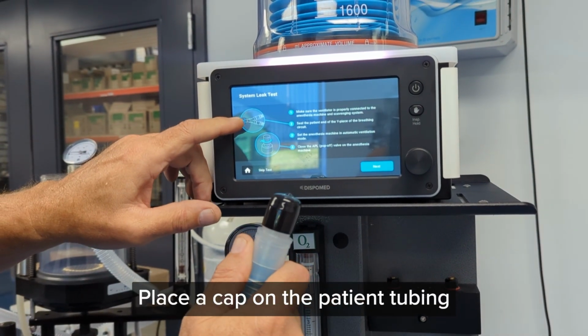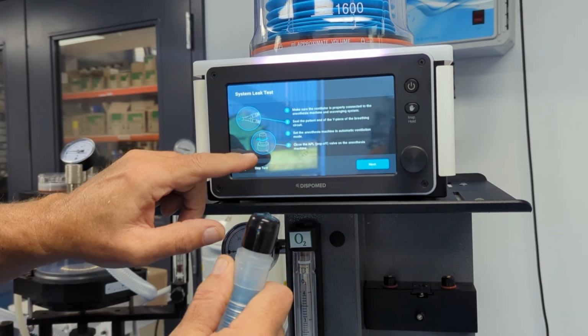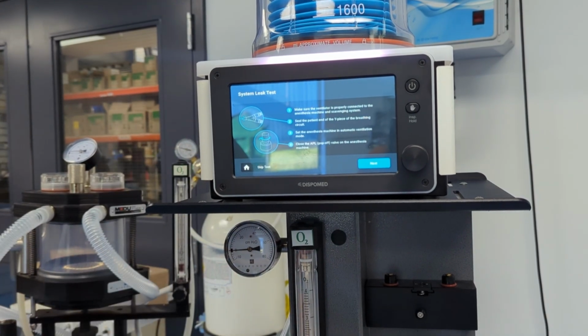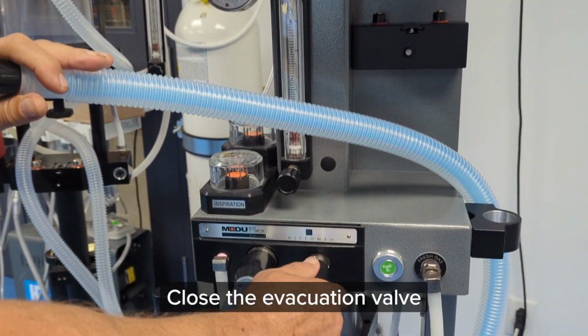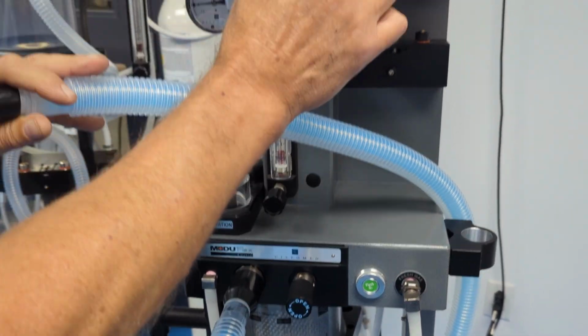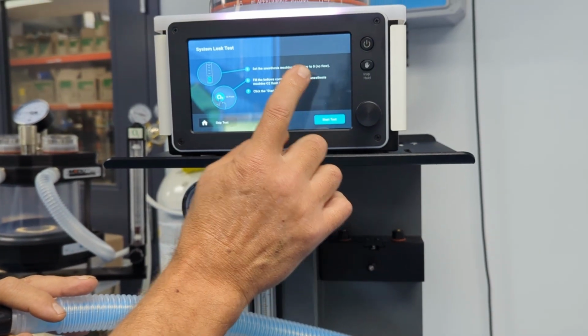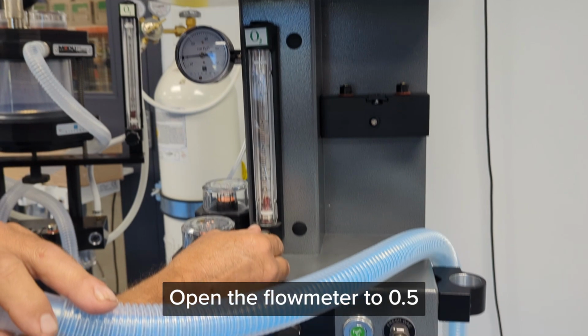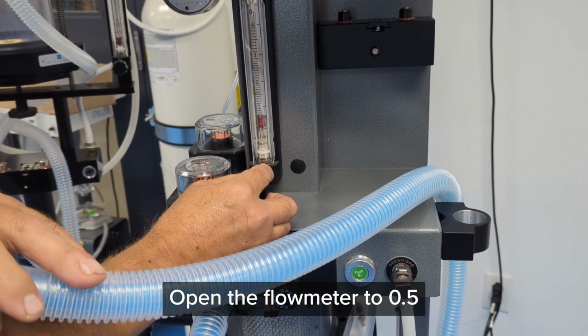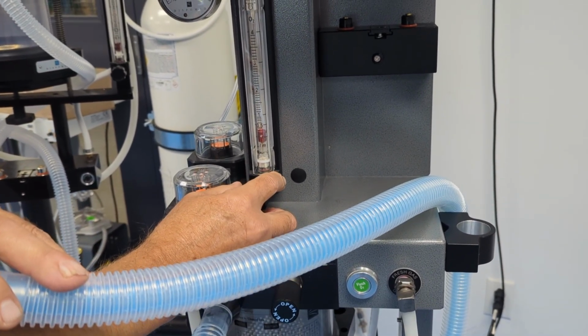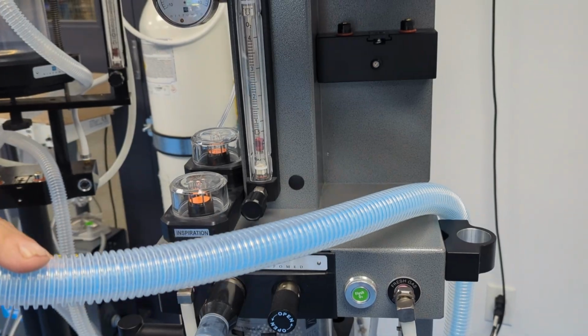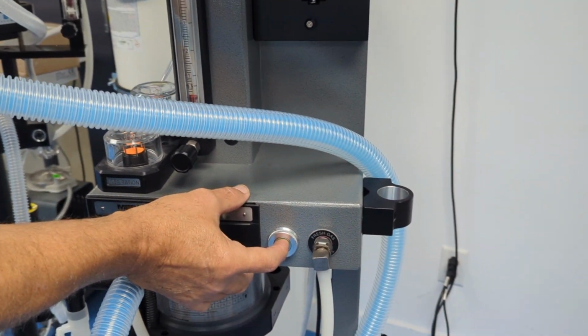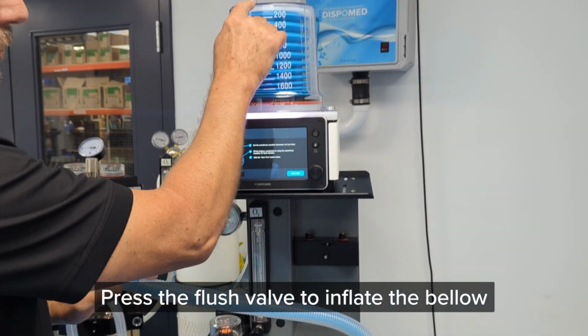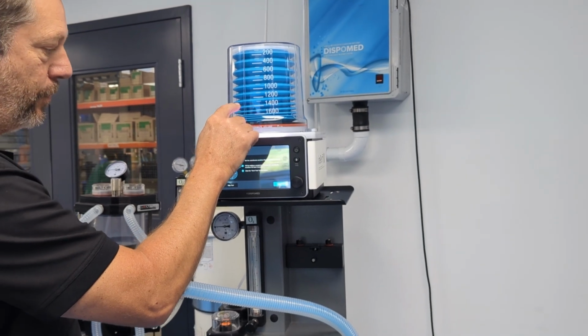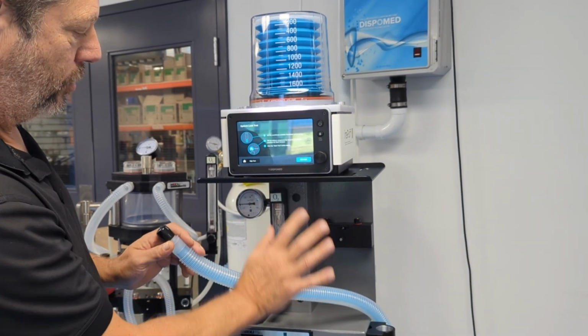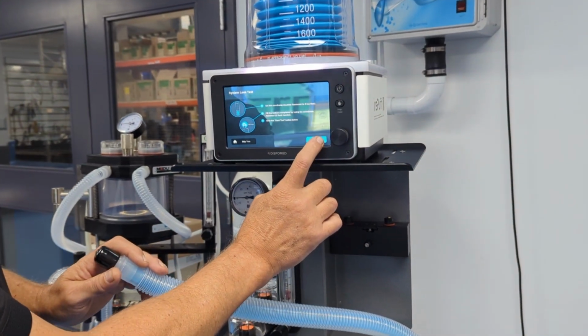Place a cap on the patient tubing. Close the evacuation valve. Open the flow meter to 0.5. Press the flush valve to inflate the bellow. Start the test.